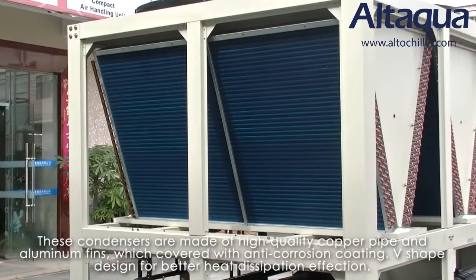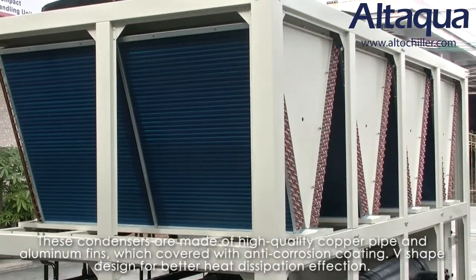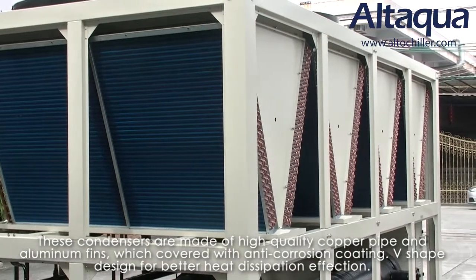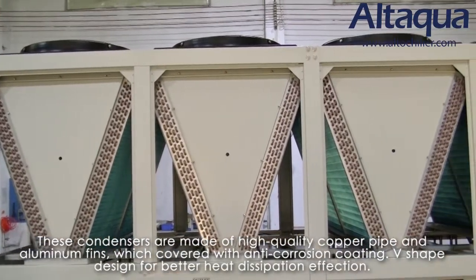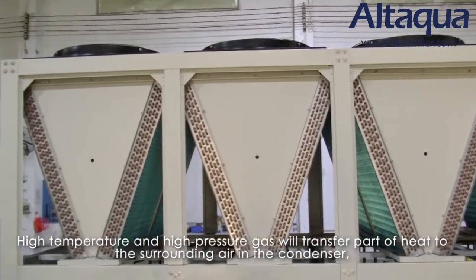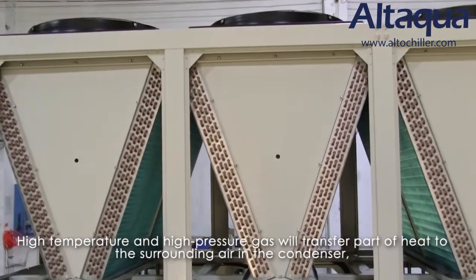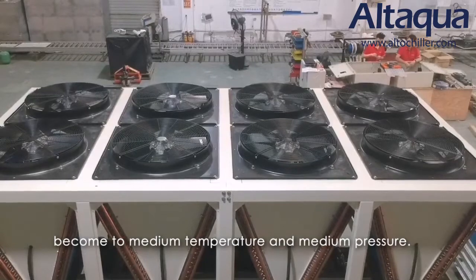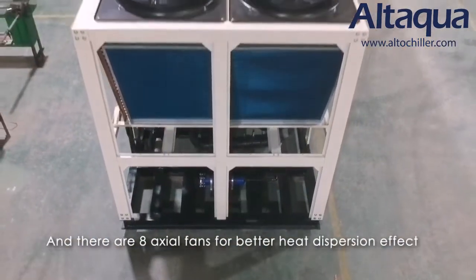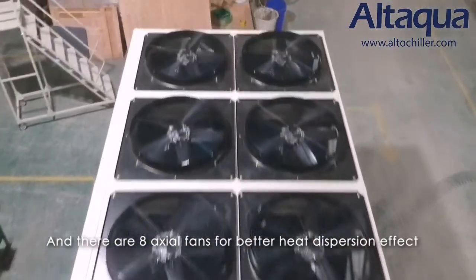This condenser is made of high-quality copper pipe and aluminum fins, covered with anti-corrosion coating, and features a V-shaped design for better heat dissipation effect. High-temperature and high-pressure gas will transfer part of the heat to the surrounding air in the condenser, coming to medium-temperature and medium-pressure. There are 8 axial fans for better heat dispersion effect.